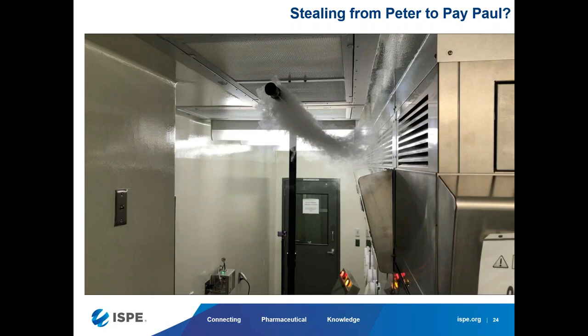But what happened? The inlet grill is right next to the HEPA filter. So what happens? We are stealing from the HEPA filter, which we call the LAF part, to feed the RABS - stealing from the LAF to feed the RABS. And what happens here underneath? We wanted it to be clean because from here we will be going into the grade A. Did we keep it clean? No, it does not - the air does not even reach halfway. So this part becomes dirty, and the people here, we shed all the time.